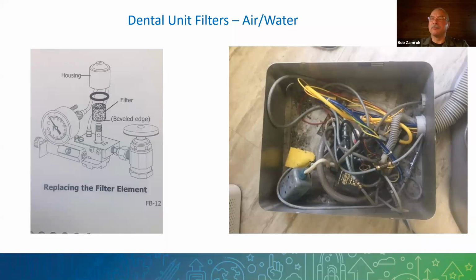My manager and I just had a meeting about this not too long ago, because this has changed since bottles were first used. The reason bottles came along was all the biofilm that built up in the tubing, so initially everyone recommended either sterile water or distilled water so you didn't have any impurities at all. Now they're starting to change that, and some manufacturers say highly filtered water or distilled water, or potable water, whichever is acceptable drinking water in your area.